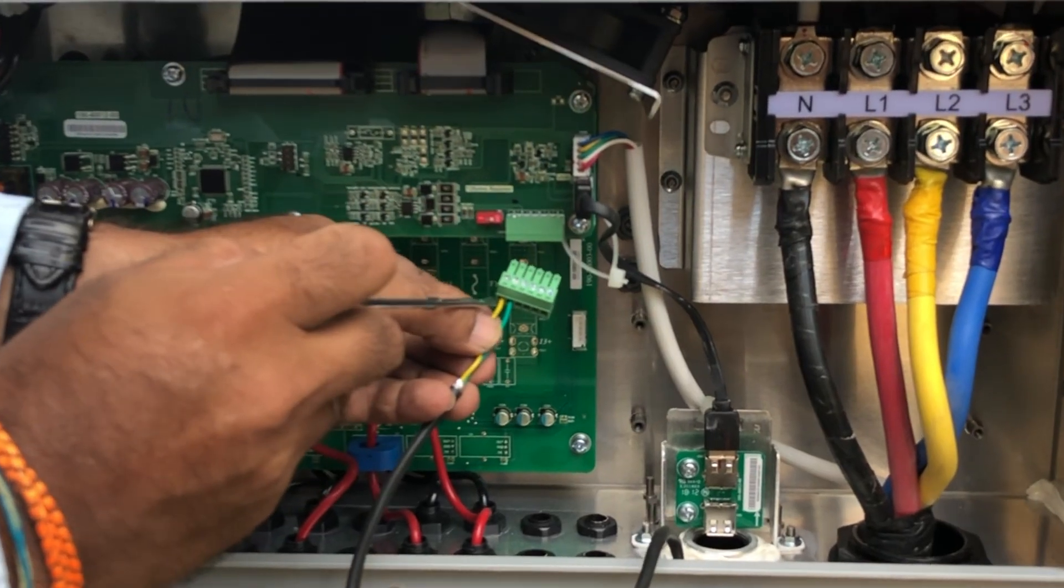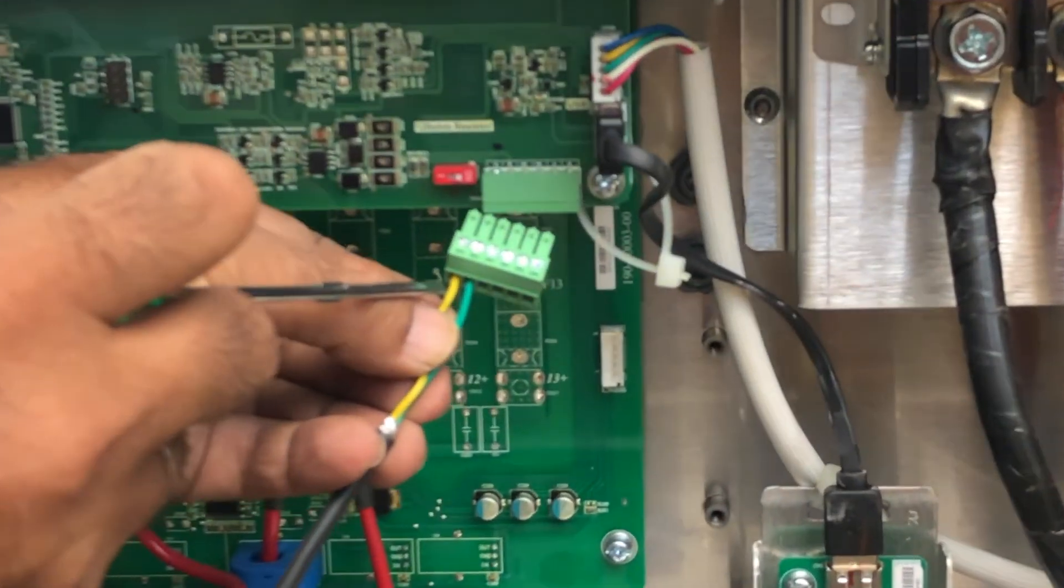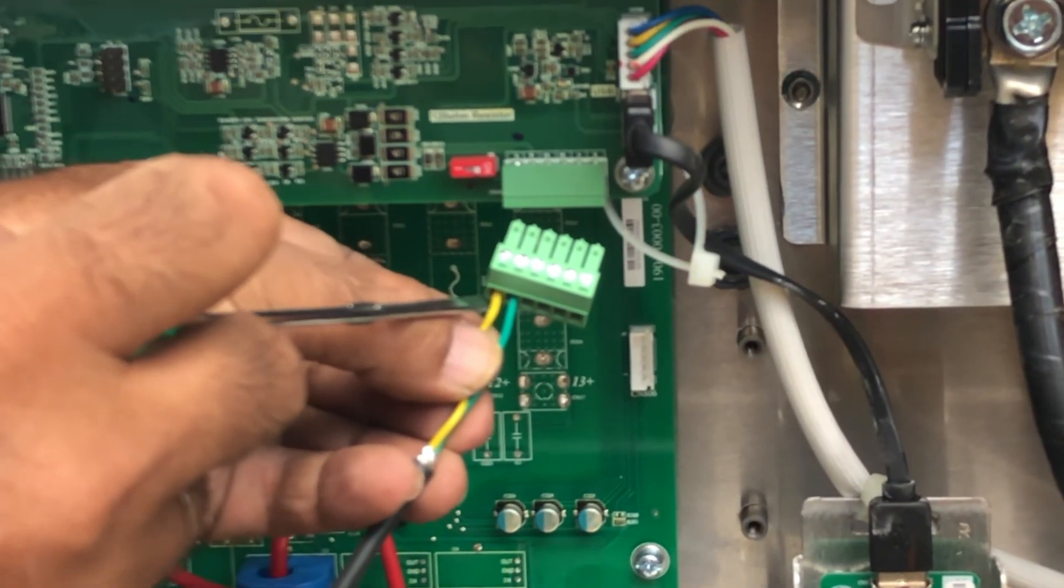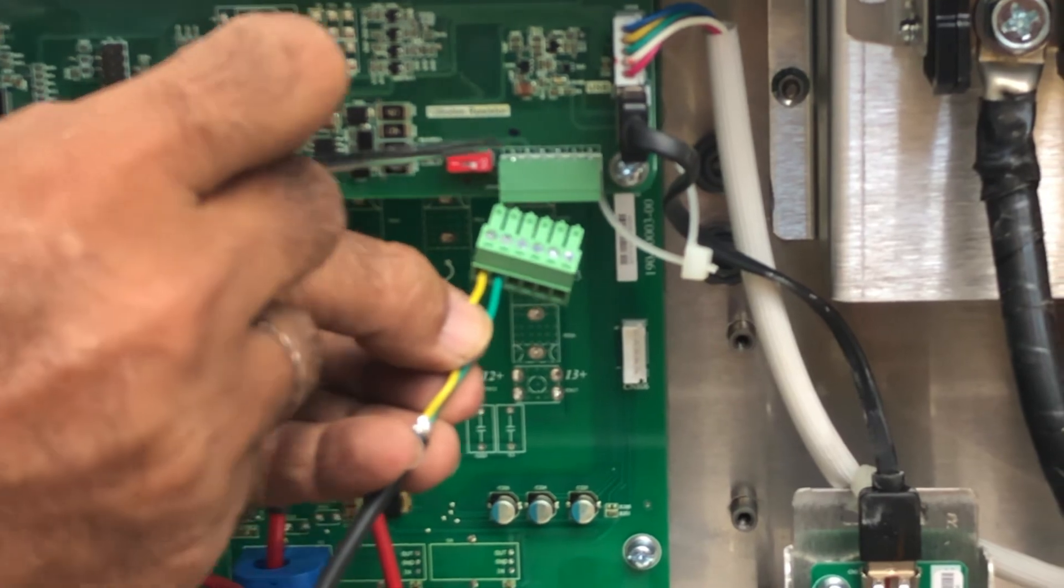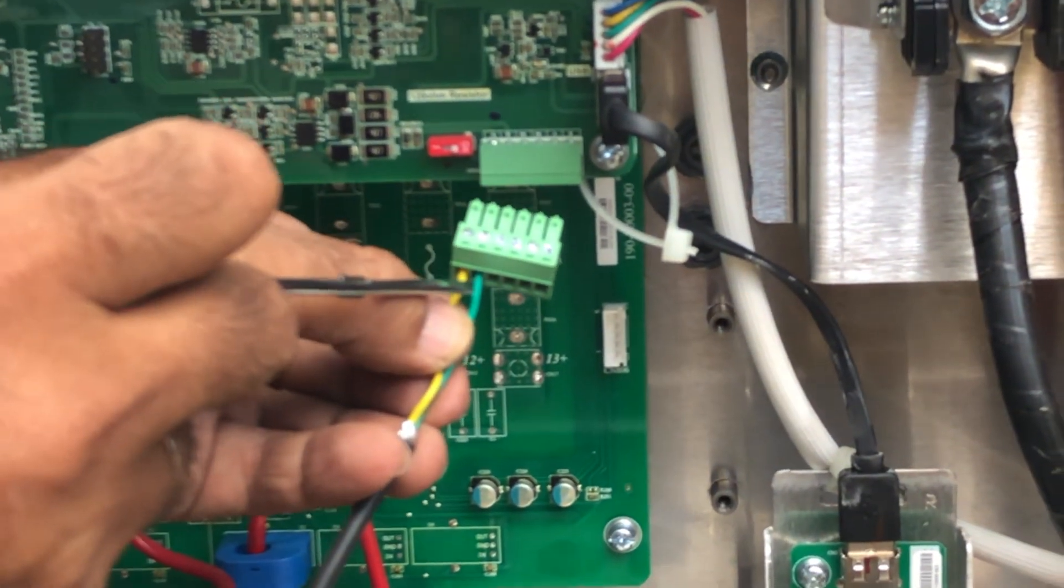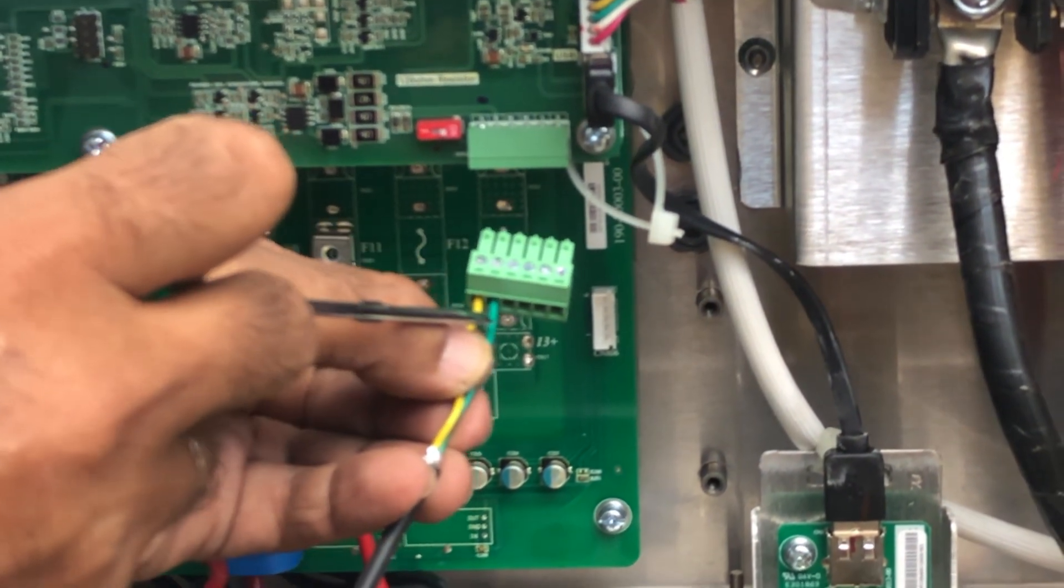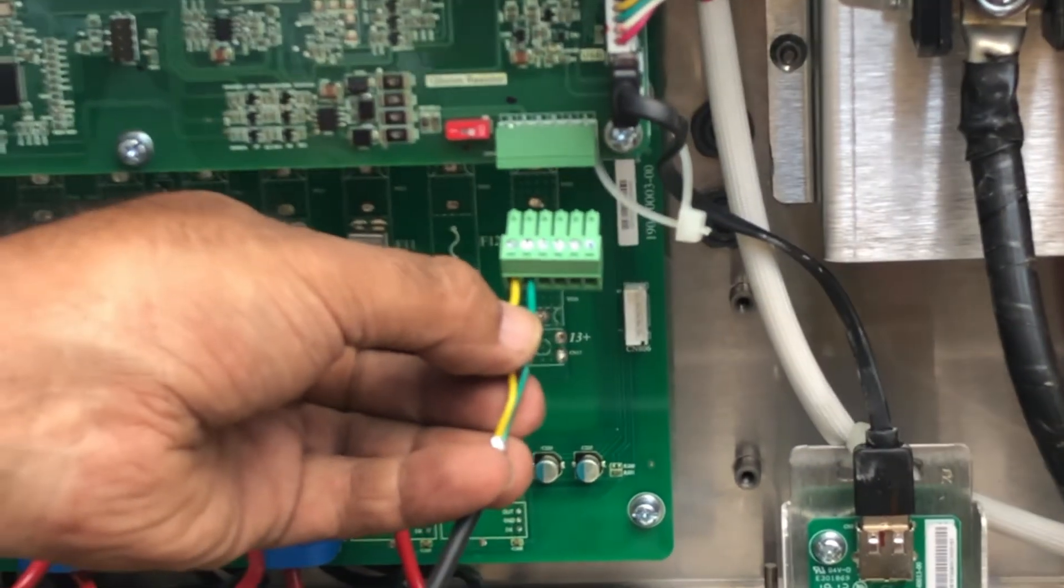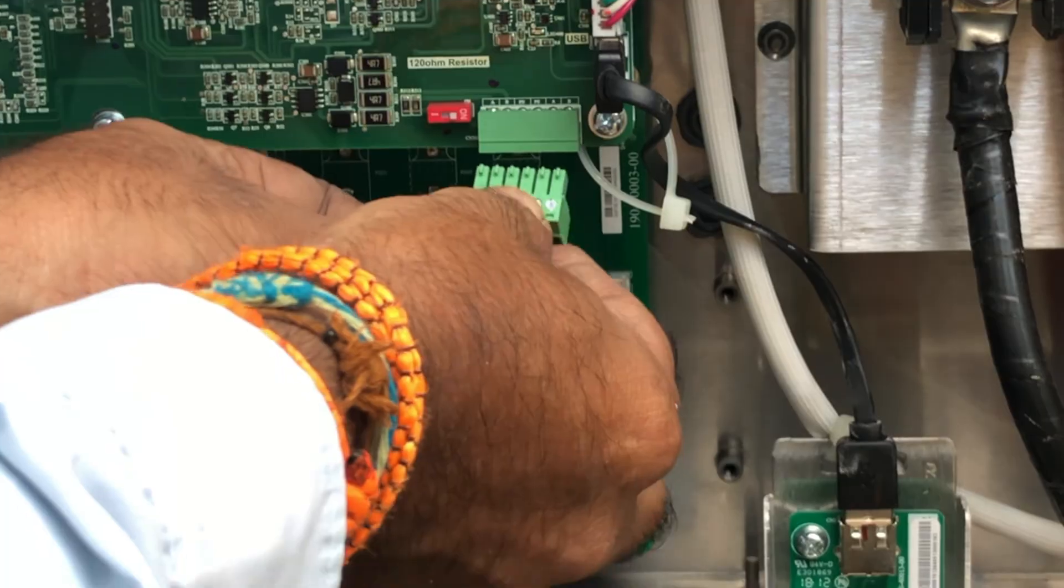From the data logger comes the yellow which gets connected to the RS 485 plus, and the green wire to the RS 485 minus of inverter.